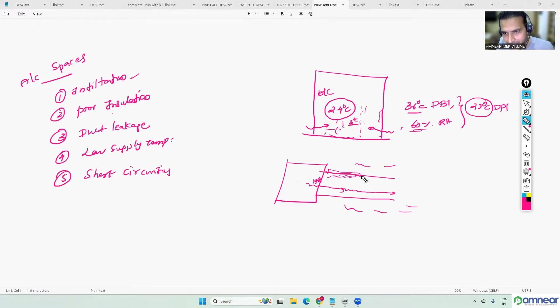Even if we have proposed thermal insulation, and if the thermal insulation is not proper, what will happen? Due to the presence of cold air, the cold air is having contact with the duct surfaces. After some time, the metal duct surface temperature will be decreasing. As you know, let's say the dew point temperature of the surrounding air is 22 degrees Celsius, but the duct surface temperature is nearly 14 degrees Celsius, for example. So when this 22 degrees Celsius dew point temperature air is having contact with the 14 degrees Celsius duct surface, the temperature of the duct surface is much lower than the dew point temperature of the surrounding air. So the dew will get accumulated on the duct surface, and this dew will be dripping down.